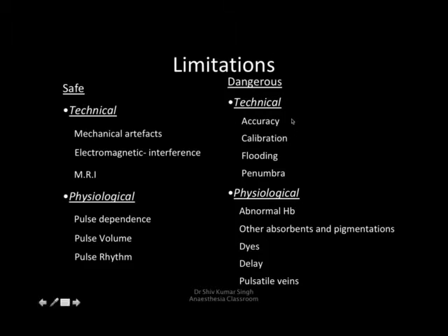Like I mentioned, the calibration occurs using volunteers who cannot be desaturated below 80%, so the accuracy below 80% is reduced. Flooding and penumbra can actually affect the reading. This is seen when you use a large probe on a small finger, like in pediatrics. Ambient light can affect the reading, and that's why we should be sure that either the probe is covered or you use the right size probe. And then there are other physiological limitations like abnormal hemoglobins, absorbance, and pigmentation, dyes, delays, and pulsatile veins.